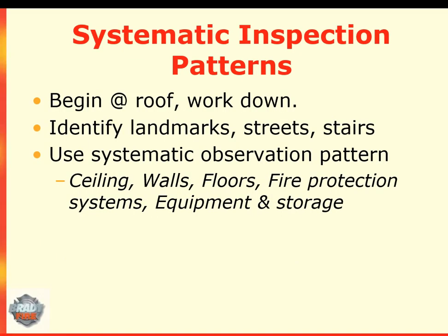Always use a pattern of movement and record information to permit better organization of information in the report. Begin at the roof and work down. Maintain a consistent pattern of movement clockwise or counterclockwise, identifying landmarks or streets, anchor points such as stair numbers. Stair enclosures can act as an anchor point on each floor for orientation. Use a systematic observation pattern. Scan each room in 3 layers: ceiling, walls, and floors.